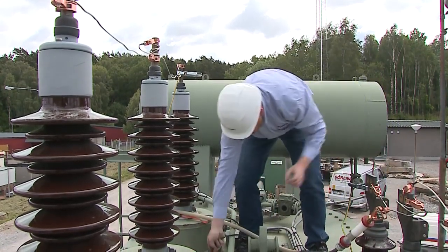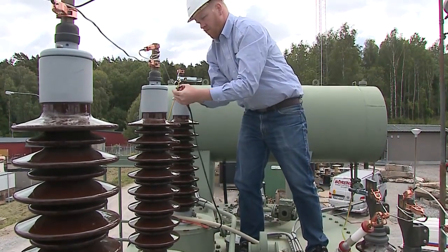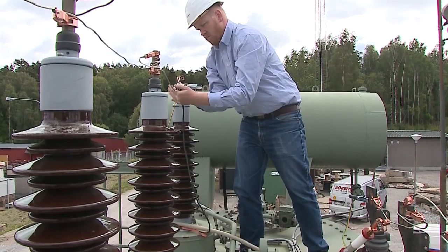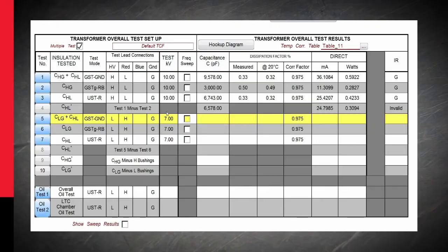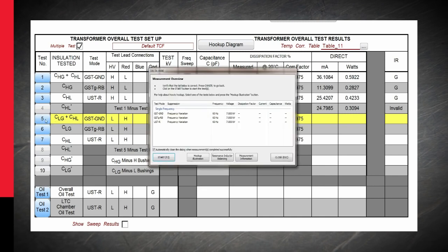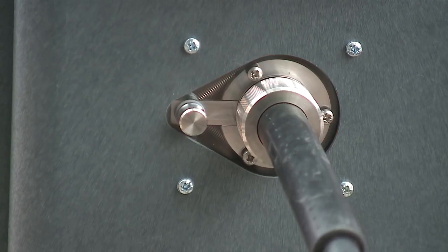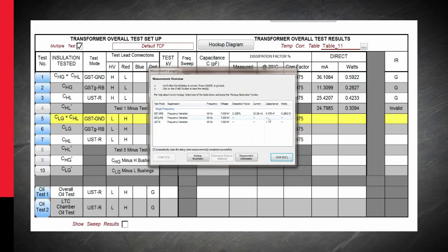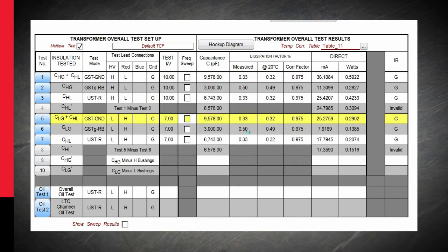We exchange the high voltage lead and low voltage red lead on top of the transformer. Ensuring that the proper test voltage is selected for the low side, we now depress the test button, which begins the second series of tests. Once prompted, we close interlocks at appropriate time, and test voltage is once again applied to transformer. We can observe the results as they are completed on the dialog box.